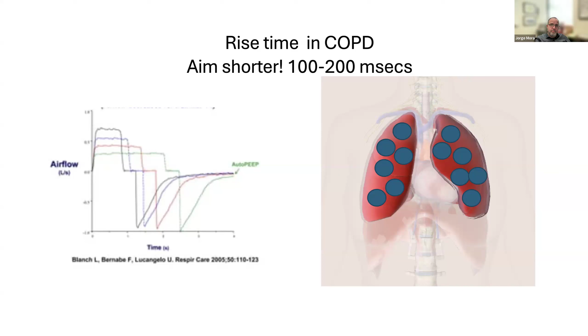If you use the same short time in patients with OHS, you're probably going to be in the wrong place. And the reason for this is that these patients, as you see on the left-hand side, have one of the issues being basilar atelectasis, which translates into those areas being essentially collapsed. If you exert the pressure very fast and in a short time, what you're going to achieve is a preferential inflation, if you want to call it this way, of areas of the lung that have larger compliance, meaning the apices. It's going to translate into asymmetrical recruitment and probably no recruitment at all at the bases. And it can actually, in a way, temporarily worsen your VQ mismatch by reducing flow in the areas that you're preferentially ventilating.